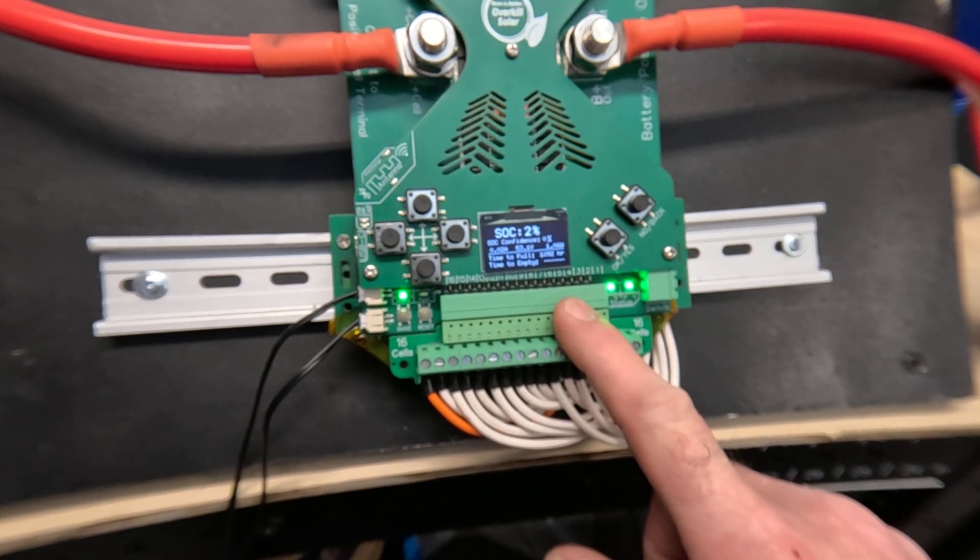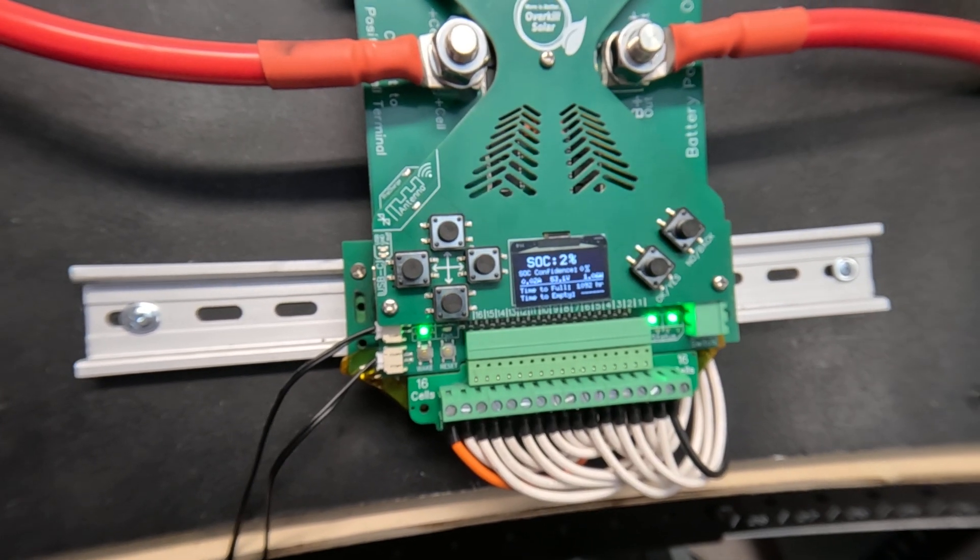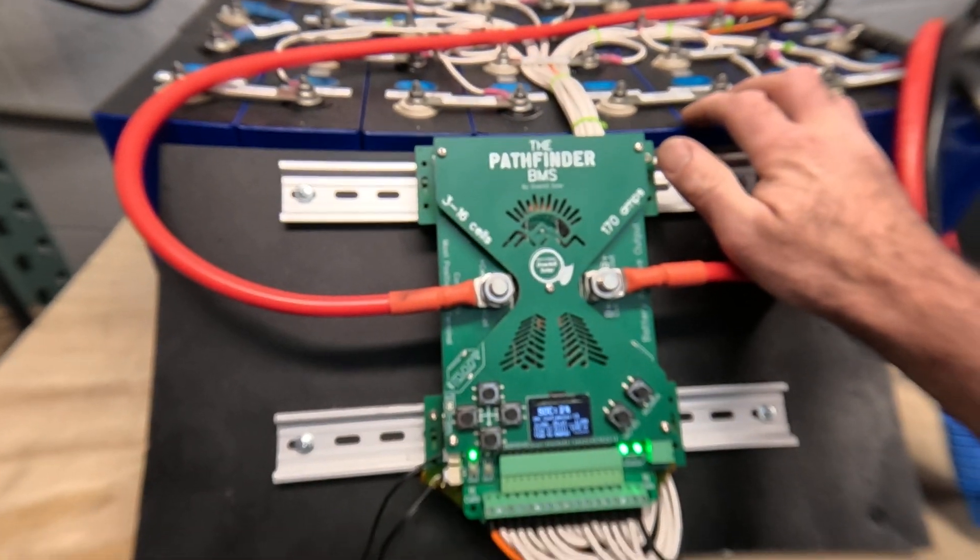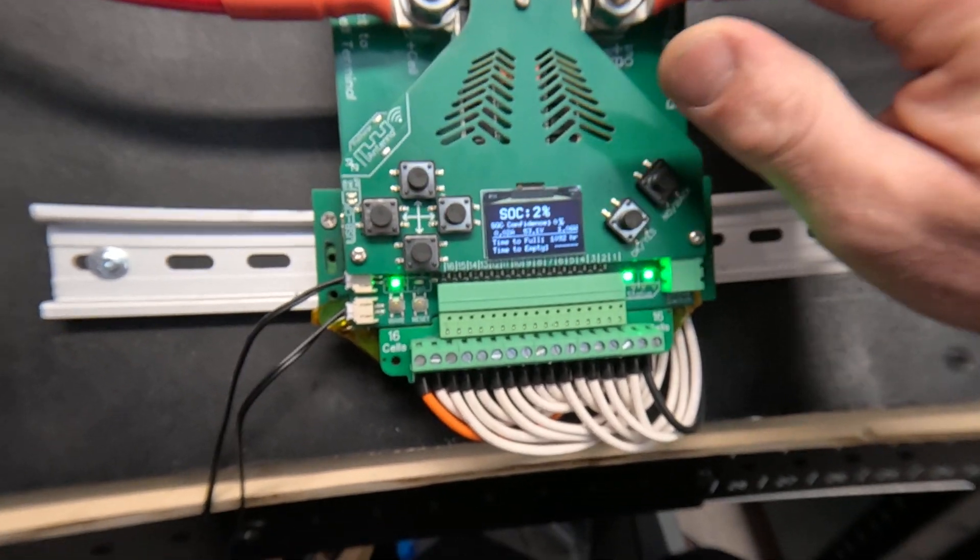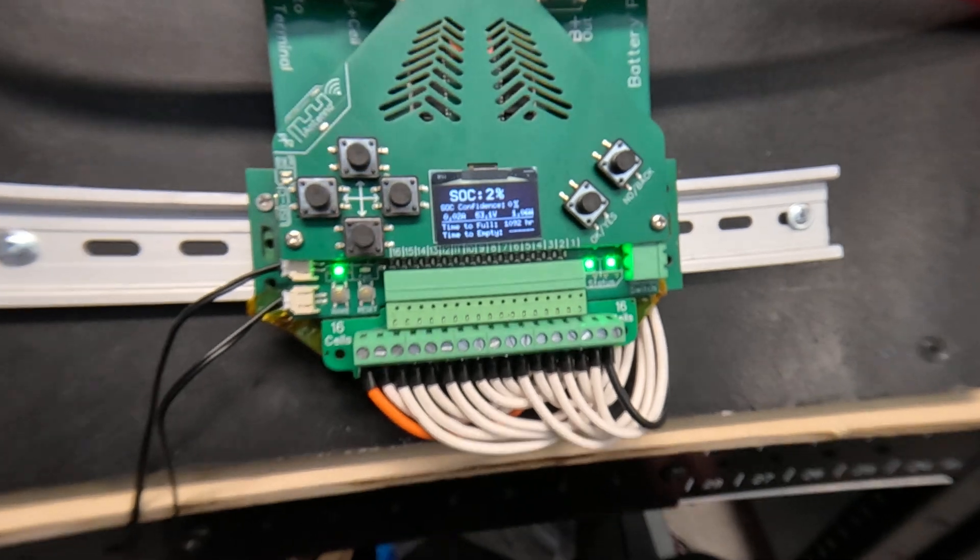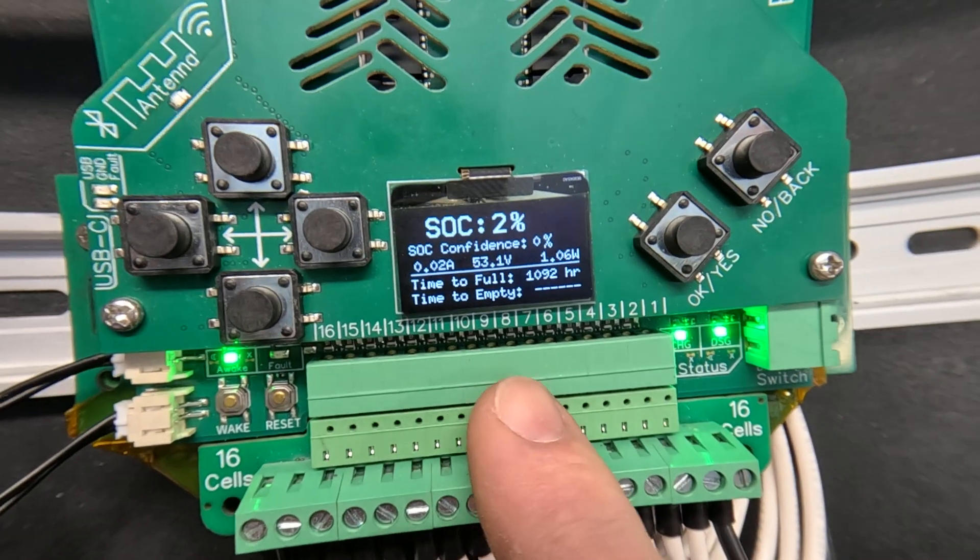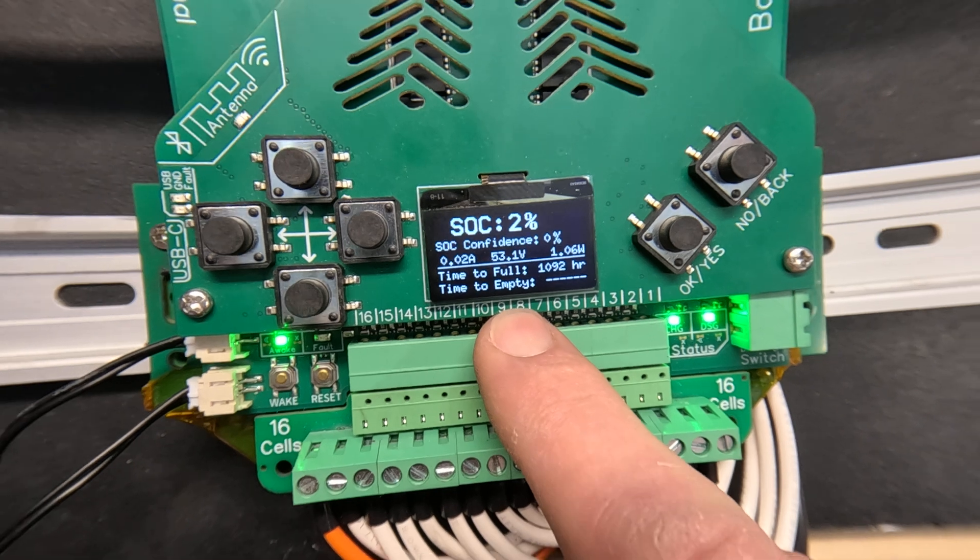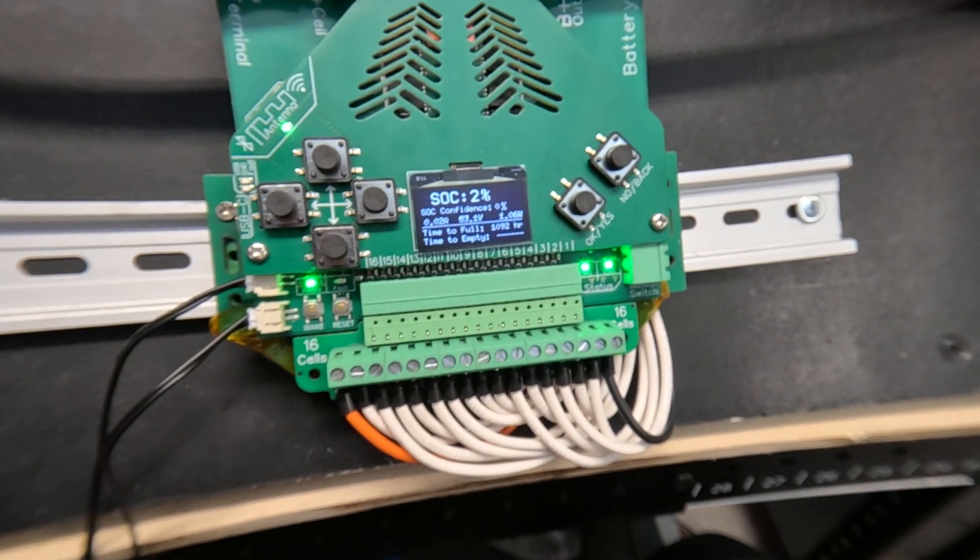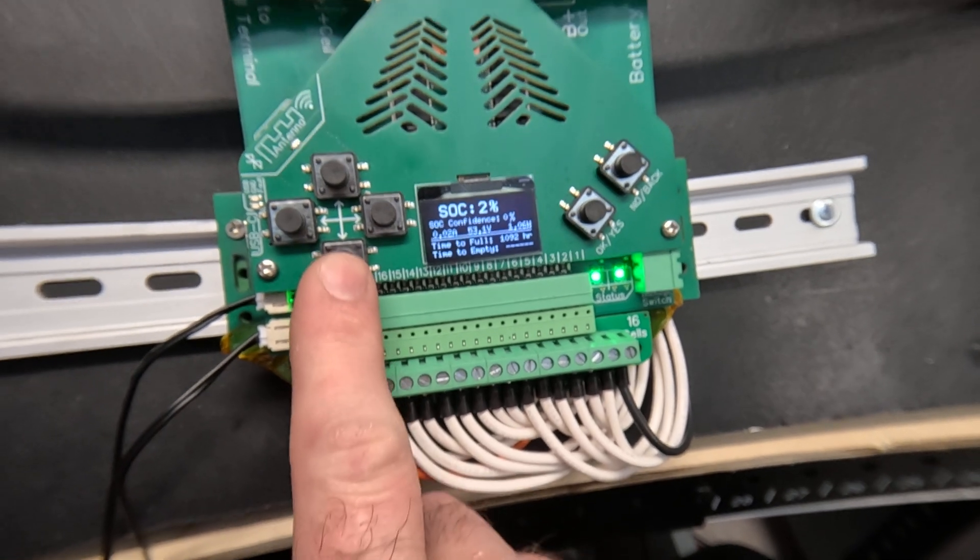It does have a learning cycle. We will be providing the baseline setup with the completed learning cycle for the types of batteries that we have available to test with, and so that should give you a good baseline for almost any battery that you will be setting up. This screen also tells you time to full and time to empty. That's based on the average current over the design capacity that you have set up.